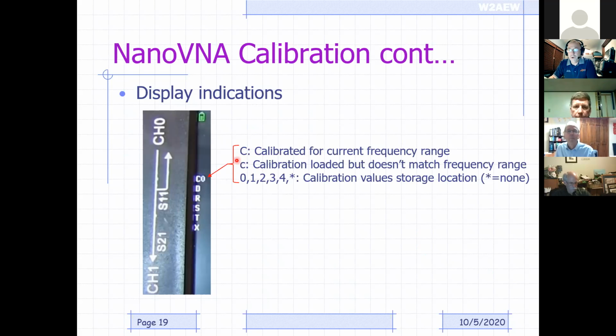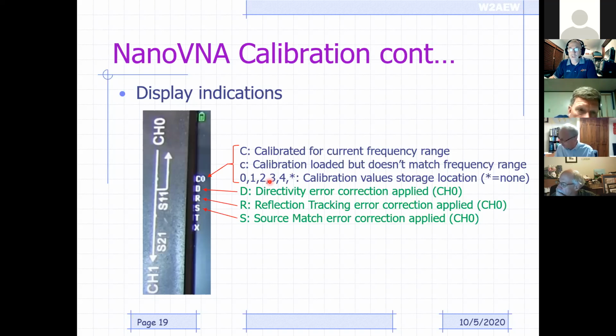If the letter is a small c, not capital C, it means that you've got a calibration over the frequency range, but it's not exactly the same frequency range. So it's doing some interpolation. That's what the small c means. The number following that tells you which slot that calibration setup is loaded into, so you can recall it later on. Okay. The next three letters, D, R, and S, stand for directivity, reflection, and source.